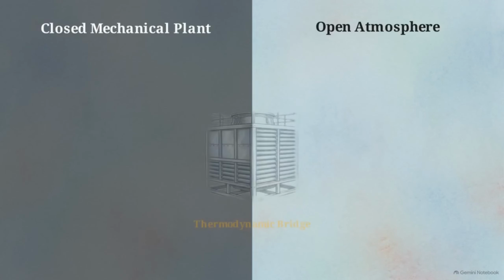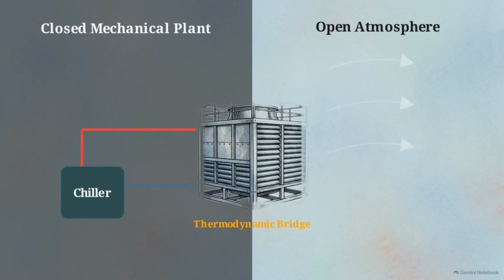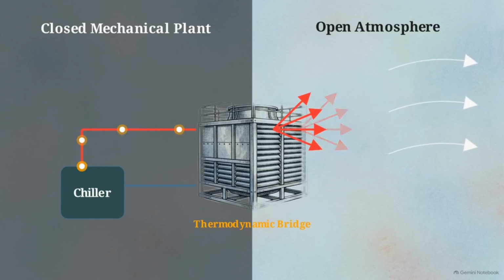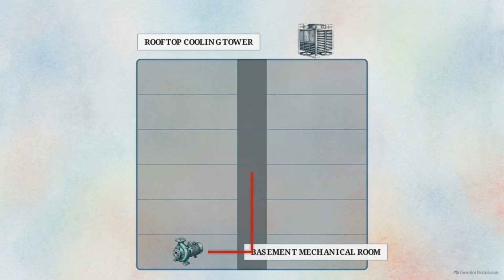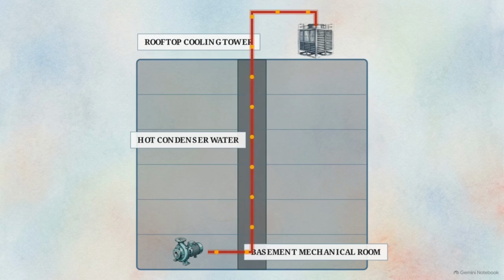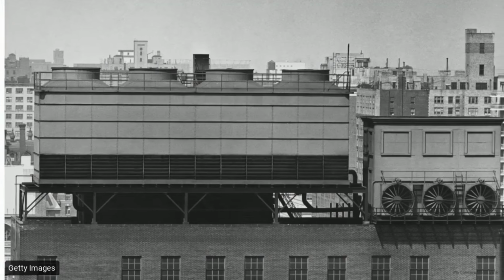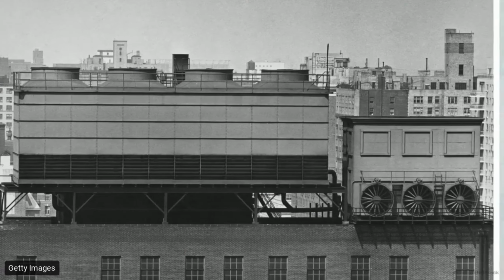The solution is a cooling tower, a dedicated heat rejection system acting as the thermodynamic bridge between the closed mechanical plant and the open atmosphere. Pumps push the hot condenser water out of the basement mechanical room and pipe it up to these structures, typically located on the roof. Up here, these massive structures take over the process.